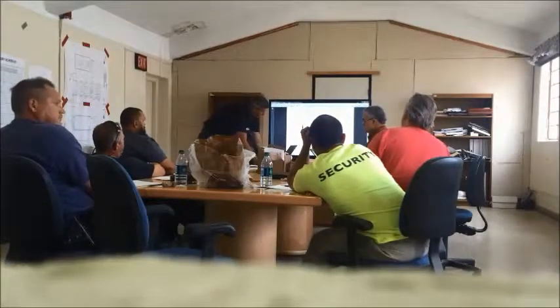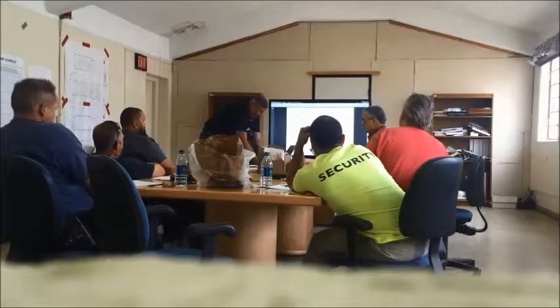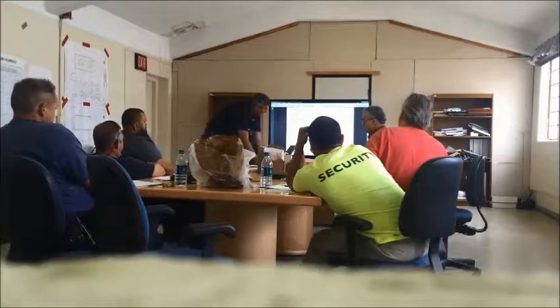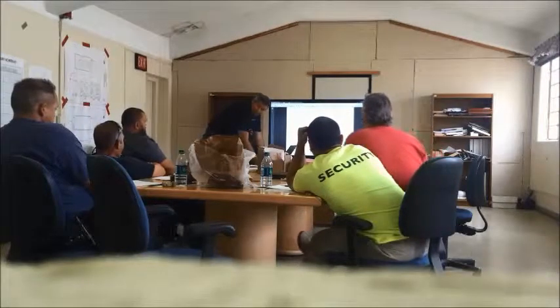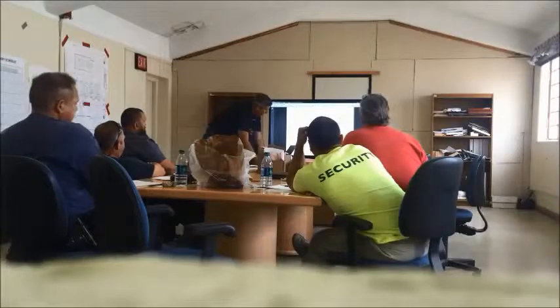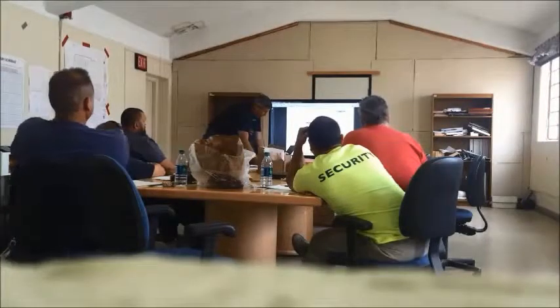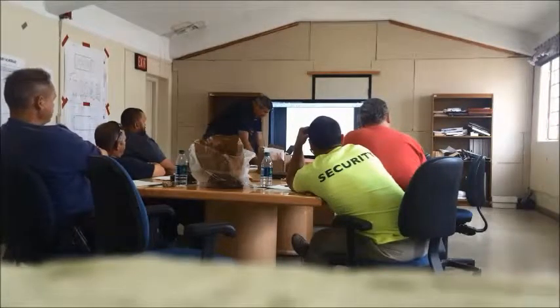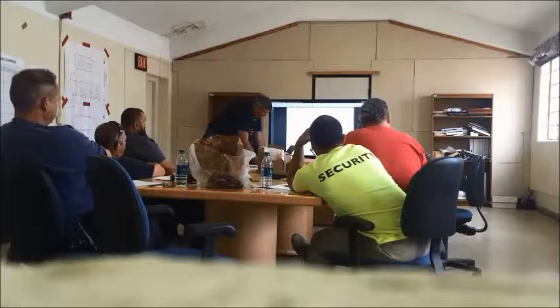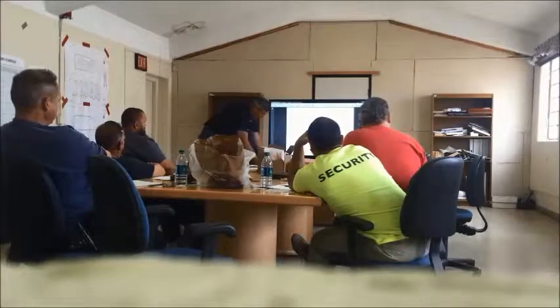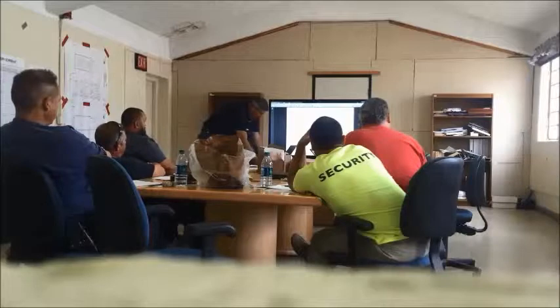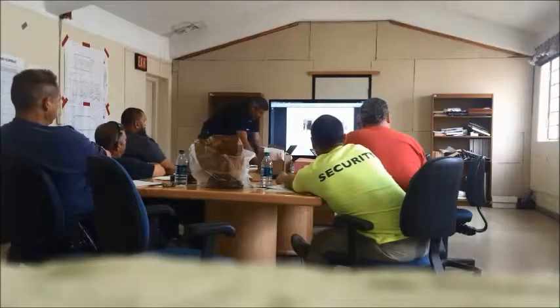So, sit on the startup or whatever. Yeah, the min-max values are set the same on those drives, and it's going to show up in our startup documentation that shows that's the condition. So if you don't have any other questions on it, then we go into, scroll down here. Okay, so about analog inputs and outputs and how the jumpers are set in those drives and those kinds of things. You have your ABB keypad, all the parameters that are associated to them.